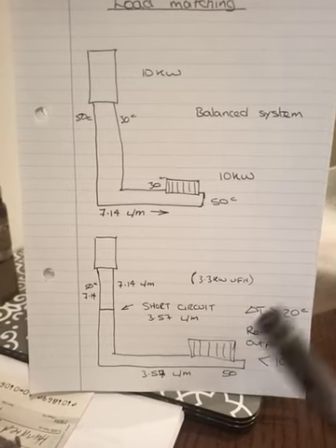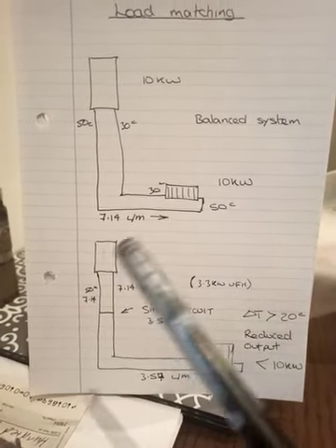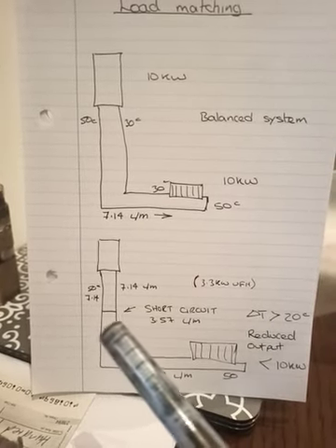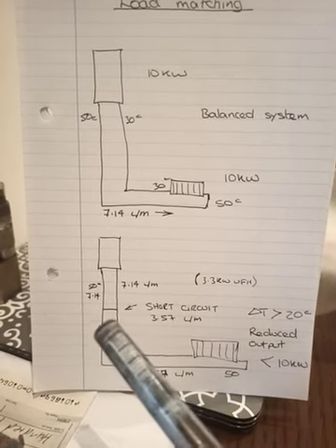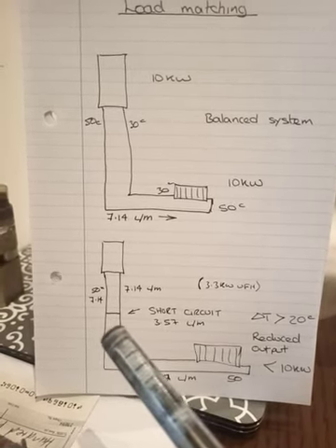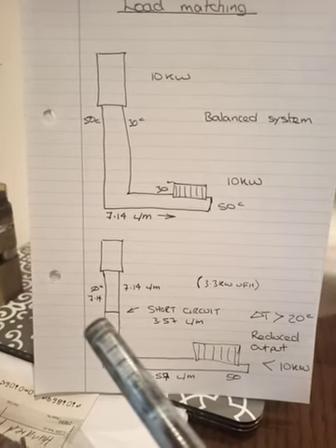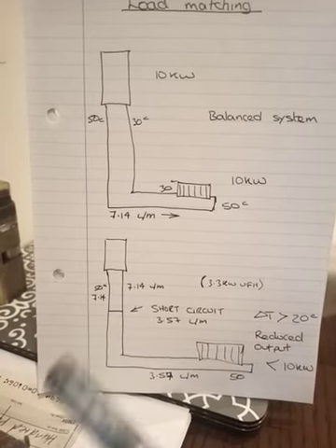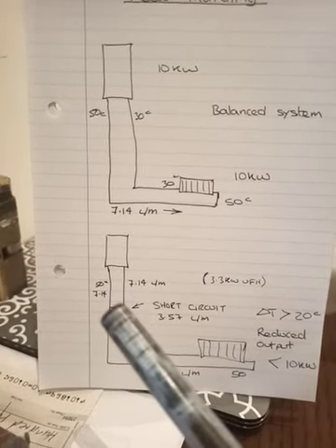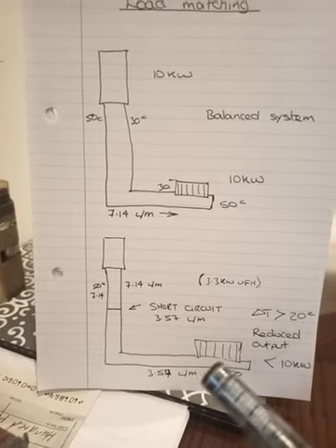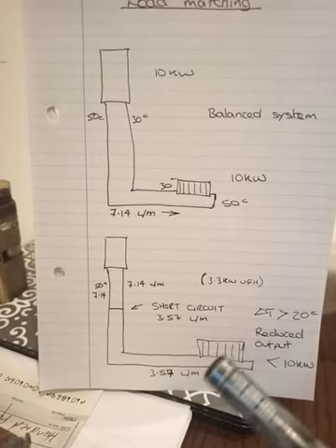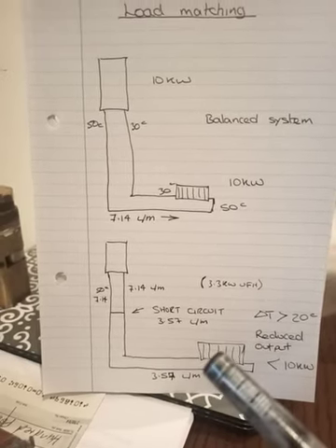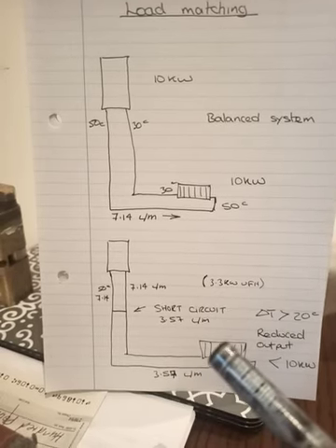in parallel. Now, the reason that I'm trying to get this across is that if we look at a balanced system and we connect any system with a form of bypass or short circuit, as I call it, across a parallel intersection in parallel to radiators, we will get a short circuit here, a flow of water crossing through our system. And at any point that happens, we will experience an underflow to our radiator circuit. That underflow will widen the delta T across that circuit and reduce the mean water temperature at this radiator. Now, if we get that, we're going to reduce the heat output.